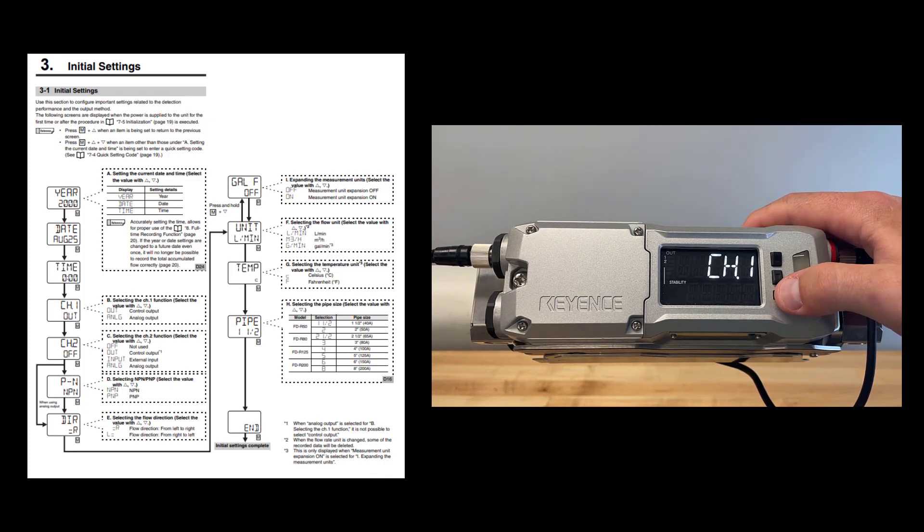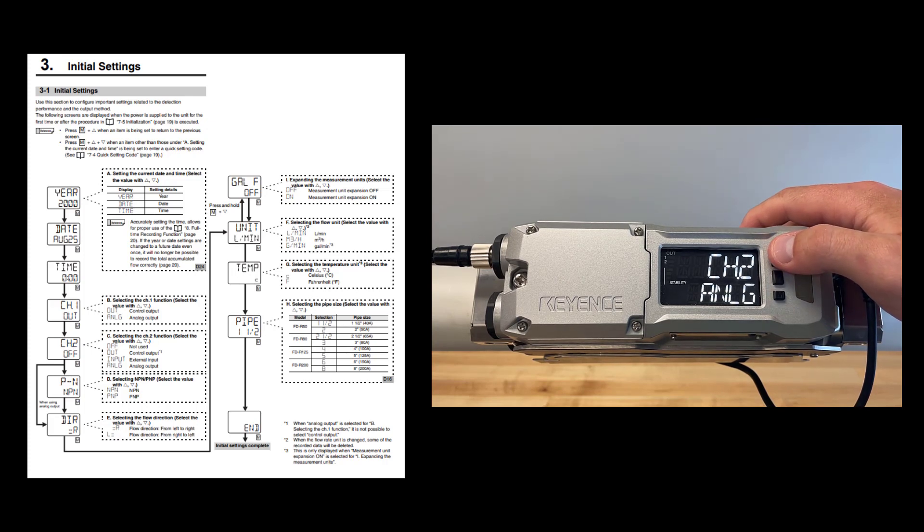Next, you can select the function of your output 1 wires being a binary output, or a 4 to 20 or 0 to 20 milliamp analog output. After that, select the function of your channel 2 or output 2 wires being off, again, an analog 4 to 20 or 0 to 20 milliamp output, an external input to the FDR, or a secondary discrete output.